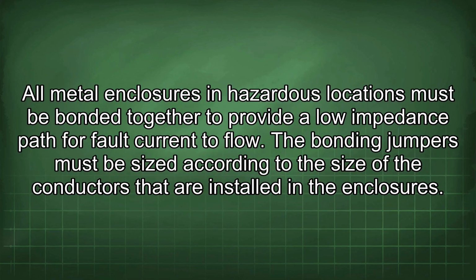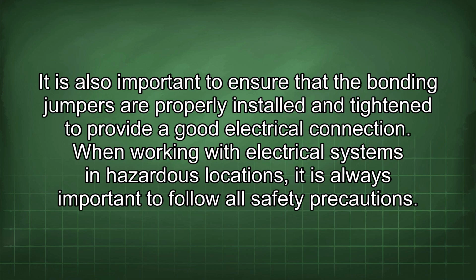All metal enclosures in hazardous locations must be bonded together to provide a low impedance path for fault current to flow. The bonding jumpers must be sized according to the size of the conductors that are installed in the enclosures. It is also important to ensure that the bonding jumpers are properly installed and tightened to provide a good electrical connection. When working with electrical systems in hazardous locations, it is always important to follow all safety precautions.